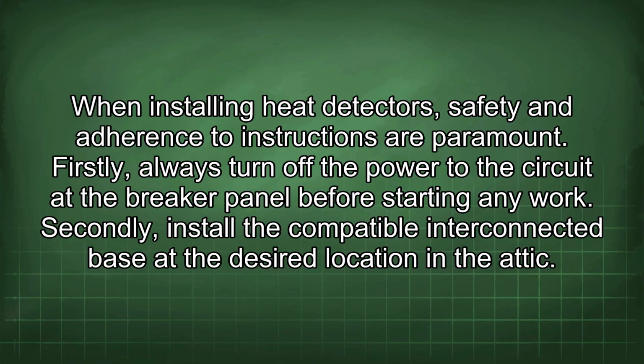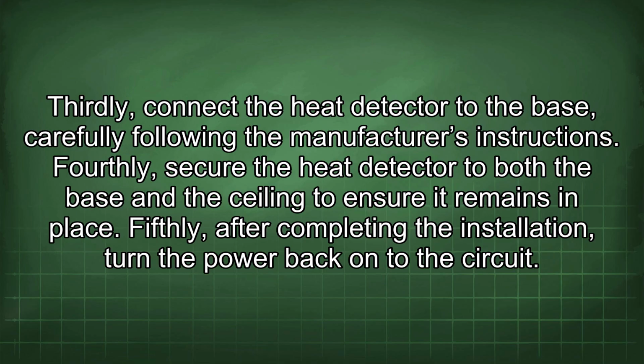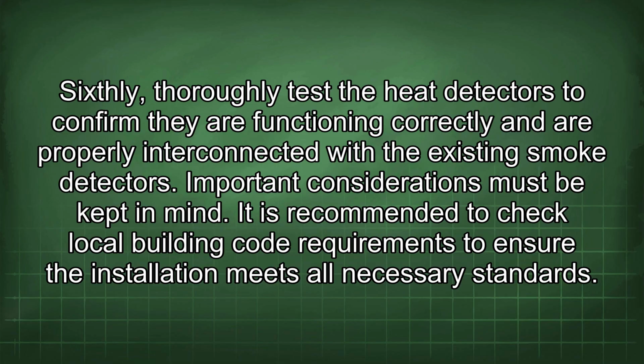Firstly, always turn off the power to the circuit at the breaker panel before starting any work. Secondly, install the compatible interconnected base at the desired location in the attic. Thirdly, connect the heat detector to the base, carefully following the manufacturer's instructions. Fourthly, secure the heat detector to both the base and the ceiling to ensure it remains in place. Fifthly, after completing the installation, turn the power back onto the circuit. Sixthly, thoroughly test the heat detectors to confirm they are functioning correctly and are properly interconnected with the existing smoke detectors.